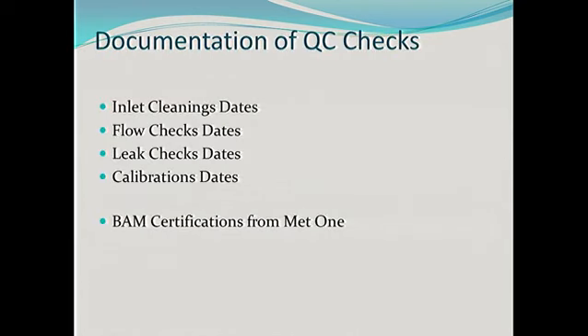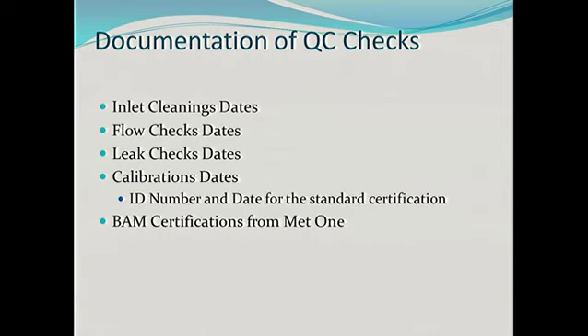Okay, we talked about all these before. All these dates have to be available when we come out there, and many times they're not. But the biggest one that we don't find out there when we come out there is the ID number of the standard that was used to calibrate your instrument, and the date it was certified. So those are the hardest things to find. The best thing to do is, as the operator, should write those down and not wait for your calibration sheet to come to you. Because many times there could be a 2-month delay by the time you get your calibration sheet from the time that we come out. So, especially if you were calibrated right before we came out.